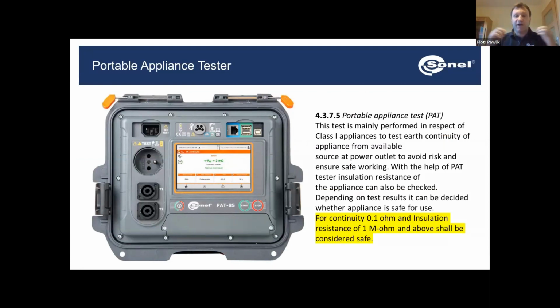Well, there's the PE wire in the power plug of our device, the power cable. And here it is also a good idea to check its continuity. That we can do with the portable appliance testers. We're going to connect our electric device to the socket on the face of the meter, and then with the probe touch the accessible conductive parts of the covers, so different metal parts of the covers, and make sure that this PE channel within our device is working correctly and that it is not broken.